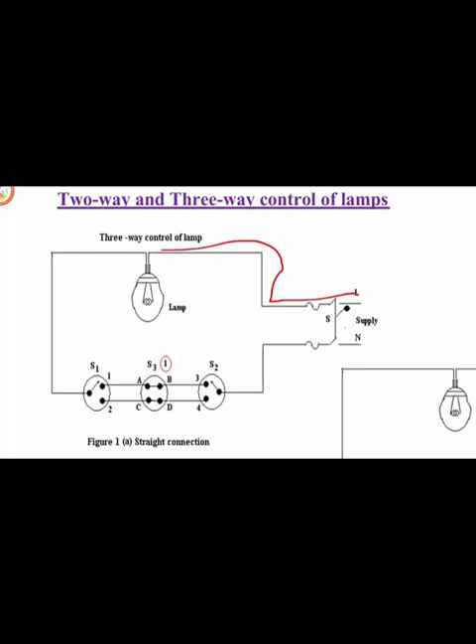In the straight connection, the line goes to the lamp, lamp to switch S1, S1 to S3, S3 to S2, and S2 to neutral. When S1 is at position one, connection goes one to terminal A, then A to B via the straight connection inside the intermediate switch, then B to three. If S2 is at position three, we have a closed path and the lamp glows — similar to the two-way lamp case.